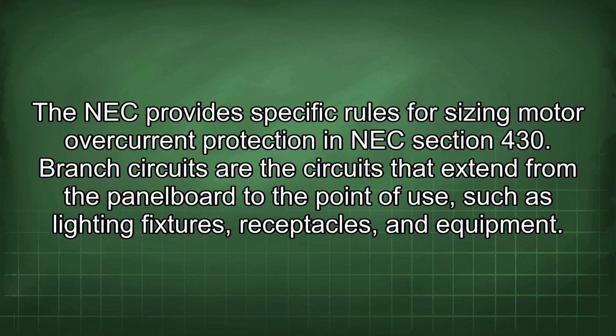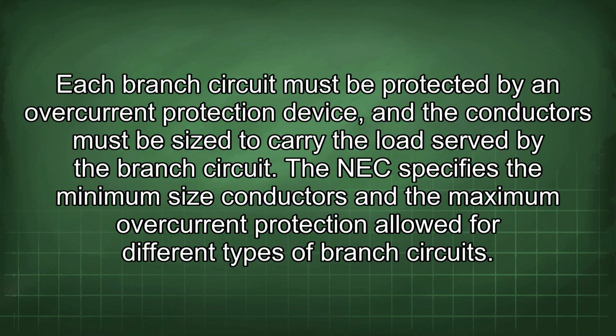Branch circuits are the circuits that extend from the panel board to the point of use, such as lighting fixtures, receptacles, and equipment. Each branch circuit must be protected by an overcurrent protection device, and the conductors must be sized to carry the load served by the branch circuit. The NEC specifies the minimum size conductors and the maximum overcurrent protection allowed for different types of branch circuits.